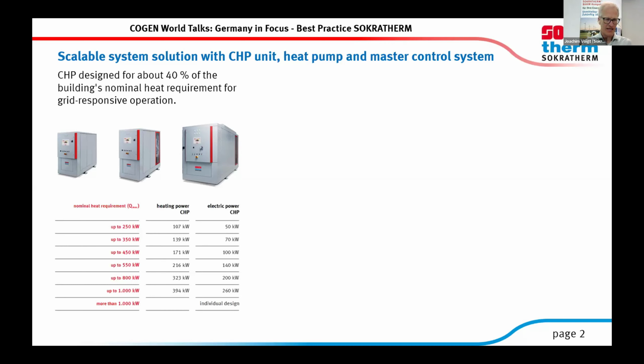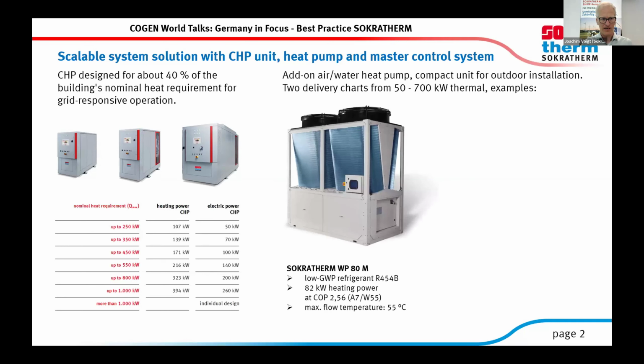this chart, and looking to bigger buildings or bigger heating networks, it's not possible to build a scalable system solution at all. You have to look for an individual design then. But for the smaller ones, this is a clever idea to combine a standard CHP unit with a standard air-to-water heat pump. We've got 2 delivery charts of heat pumps in the scope.